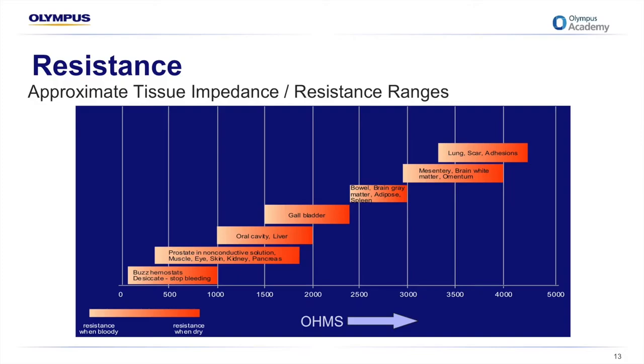And in a practical sense, in the operating theatre, it's important to note that different patient tissue has different levels of resistance. This slide here shows an example of that, where blood and fluid is very low in resistance, so it's a good conductor. And moving up the scale, tissue such as lung, scar tissue, any adhesions, that causes more resistance, so it's more of an insulator, and it's going to oppose the flow of your current, which may reduce the effect that the operator is trying to achieve. And this comes into play when we're talking about return electrode pads and where we place them a bit later on in this presentation.